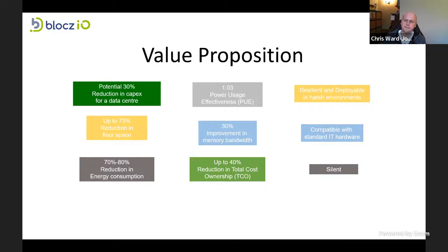So if we remove the need to run CRAC units, if we remove the need to run DX chillers on the roof and chill water, there's additional energy savings that can be made there. Another huge energy saving that people don't think about is that to immerse these servers, you have to take all the fans out. So just within the server itself, anything between sort of 25 and 45-ish% of your energy consumption, depending on the load you're running, is actually the fans just spinning inside the server. So you remove all those fans, you remove the fans from the data center.